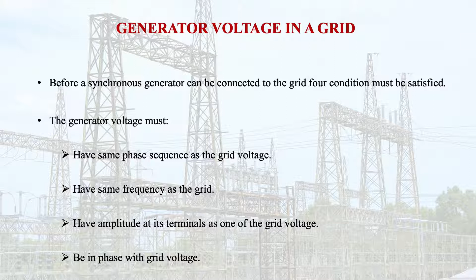So the bulk of the electrical energy is generated by a three-phase synchronous generator. You all know about this, that a synchronous generator is used in the generating power plant. Before a synchronous generator can be connected to a grid, 4 conditions must be satisfied. What are these? The generator voltage must have the same phase sequence as the grid voltage. As I discussed earlier, there should be synchronization between the synchronous generator and the system voltage, and they all should work at the same frequency. That means the generator voltage must have the same frequency as the grid. At all places the frequency should be the same.